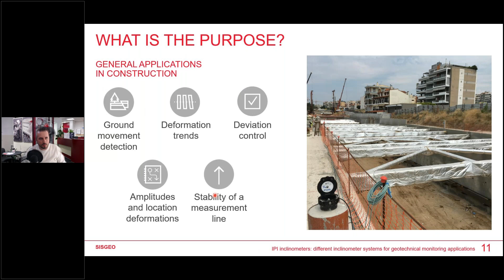So how to express the tilt? The trivial unit commonly used is the angle, expressed in radians or degrees according to the vertical vector, g. In topography, we can use the slope: meter per meter, millimeter per meter, percentage, per thousands. Commonly at Sisgeo, we express it as the sine of the angle. This sine of angle is analogous to the slope, meter per meter or millimeter per meter. It's valid for very low angles. If you have wide angles like 30 degrees or more, it's not really valid because there is a difference between the hypotenuse length and the base length. With a small angle, which is generally the case in our application, since you are measuring a differential, if this length is small, then you can express it in sine.